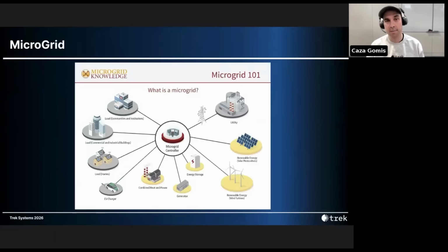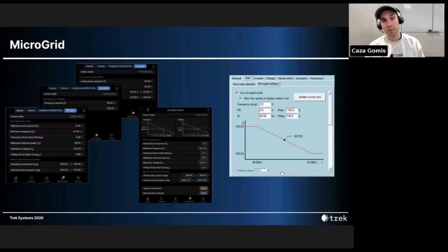Traditionally, microgrids utilize a complex and expensive energy management system, or microgrid controller, like you see in the center of the screen here, to keep all of the nodes in the network on the same page. Kind of like a GX device, except instead of managing one system, the EMS manages multiple independent systems like those shown in this example. With Victron, instead of requiring this additional management overhead, the power banks are actually able to synchronize with each other based on AC frequency and voltage.